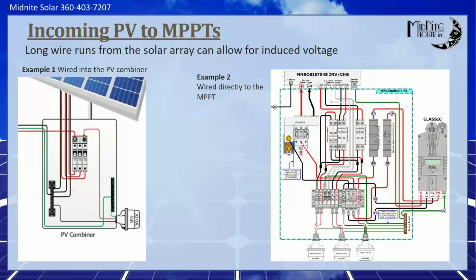So the other one we get a lot is PV to MPPTs, and this is becoming more and more of a hot topic with all the all-in-ones, and we'll go a little deeper into that in a minute. But where do you put it, right? You've got a 500-foot wire run coming in on a 600-volt PV array. Do you put it at the PV array? Do you put it at the inverter? And generally, my rule of thumb is if you're only going to do one, you put it at the inverter. The inverter is your most valuable item. Put it there. And if you can put a second one at the PV array, that's great.